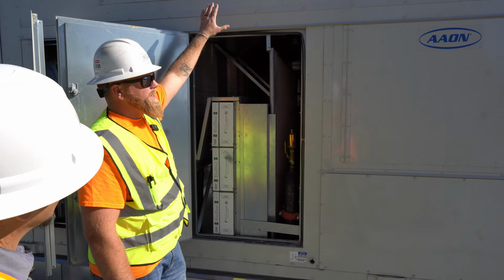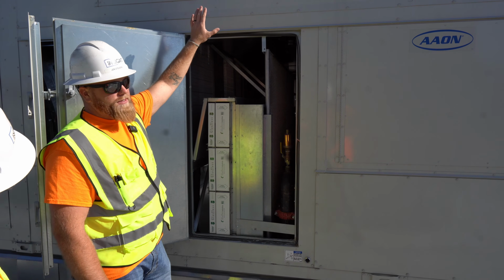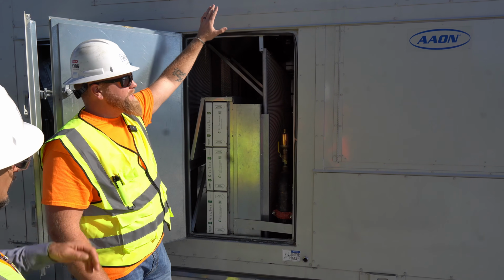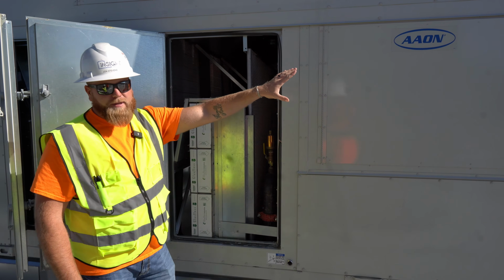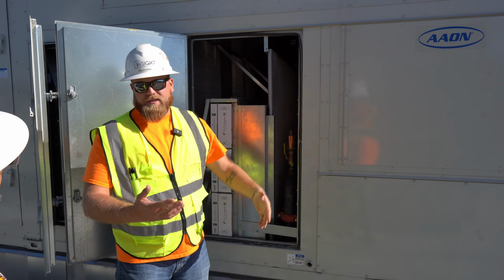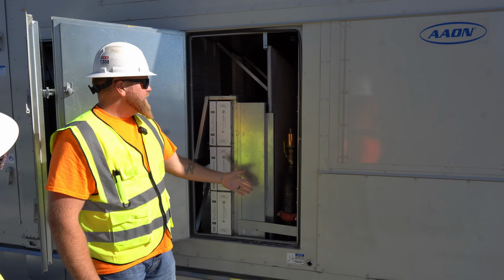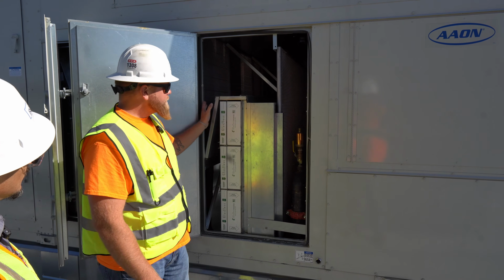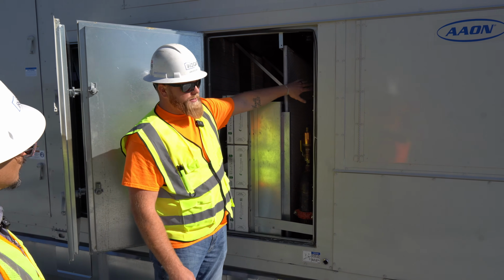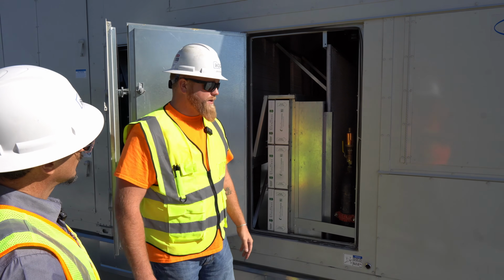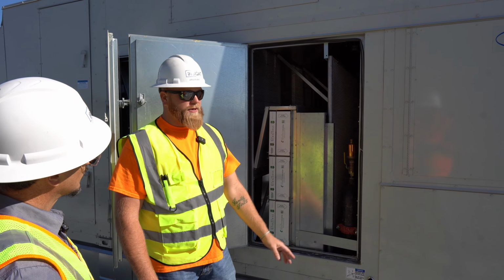Oh, okay. Gotcha. Water condenser, valves, everything is internal to the top of this system, controlled by all of those control boards up in the front, which we send set points and values to. So you're controlling your head pressure here, refrigerant flows, monitoring your discharge air temperature, and then we'll ultimately be reading the temperature and humidity off the discharge of the system.